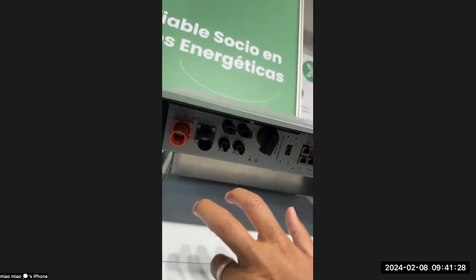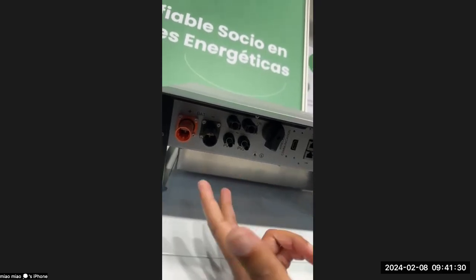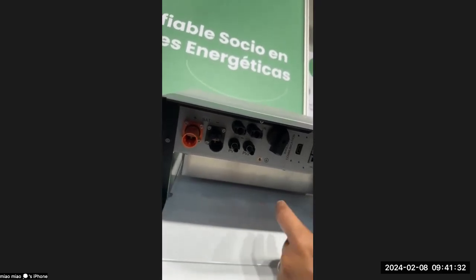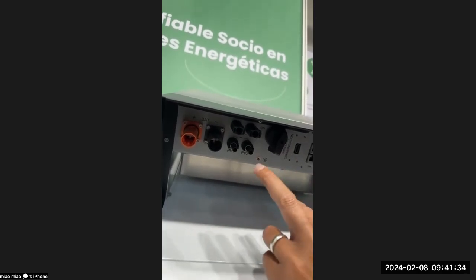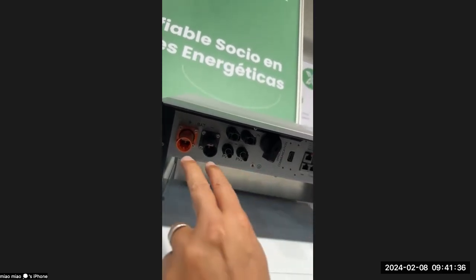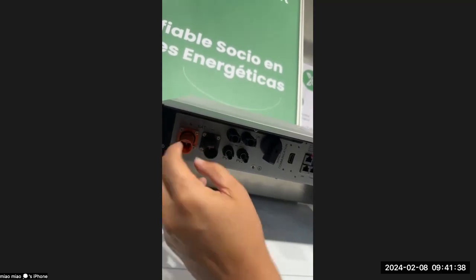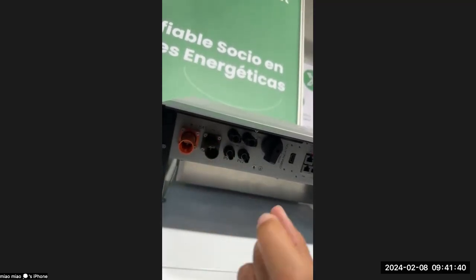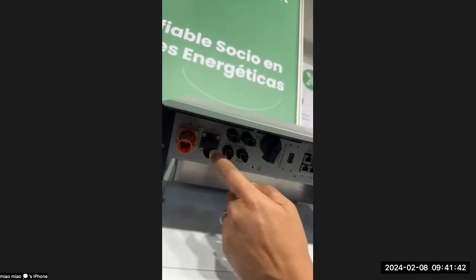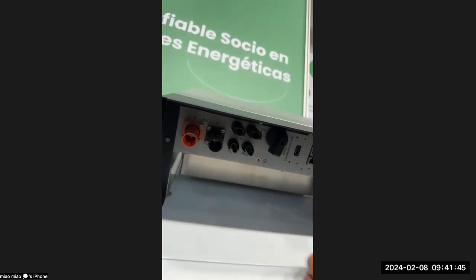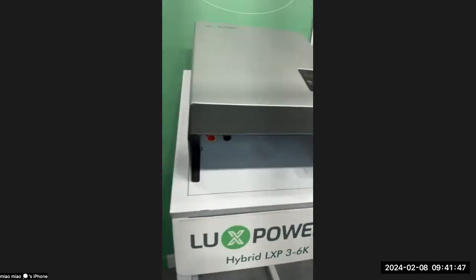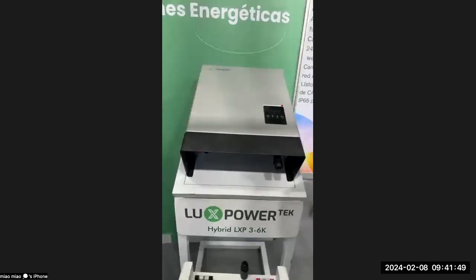If you put red on positive and black on negative, you should get a positive reading on the readout. If you get a negative reading, then it simply means that your colors are wrong. So make sure that your polarity is correct when you go inside here, and put the shrouds on as well as the rubber boots, because that's also what keeps this moisture free. Right, so that's all that we can say about the machine itself.